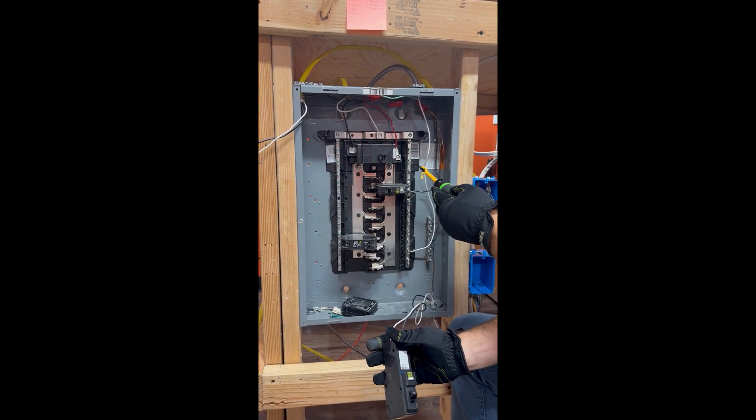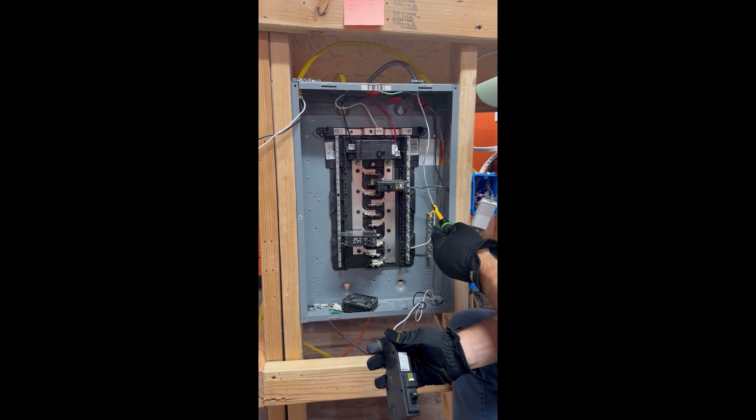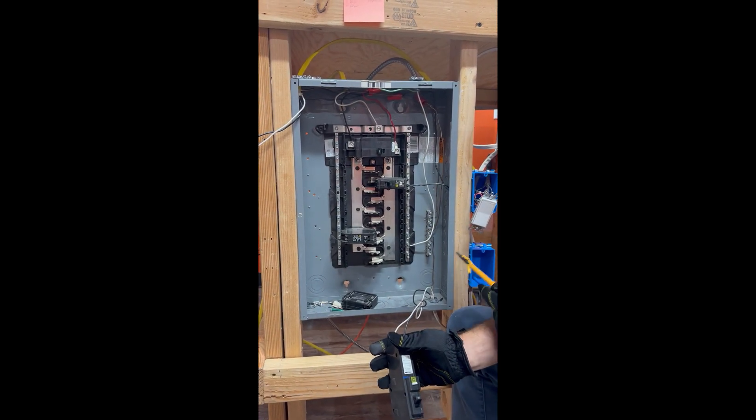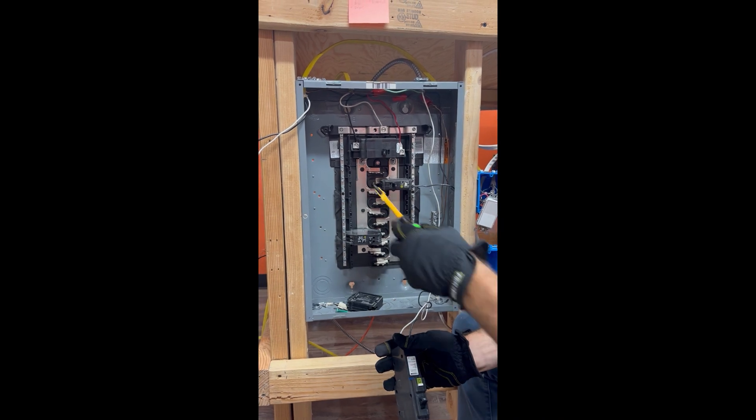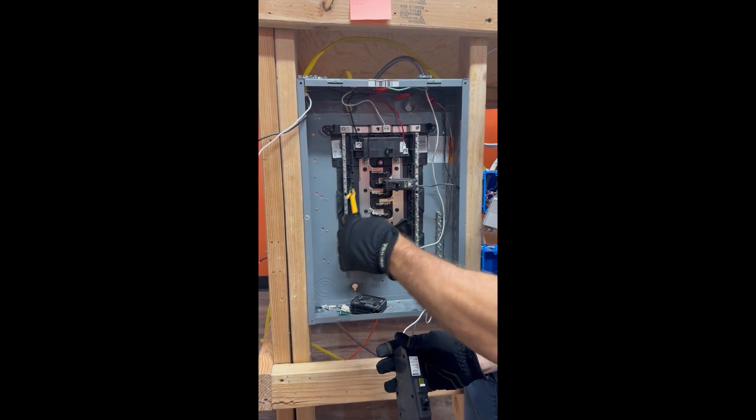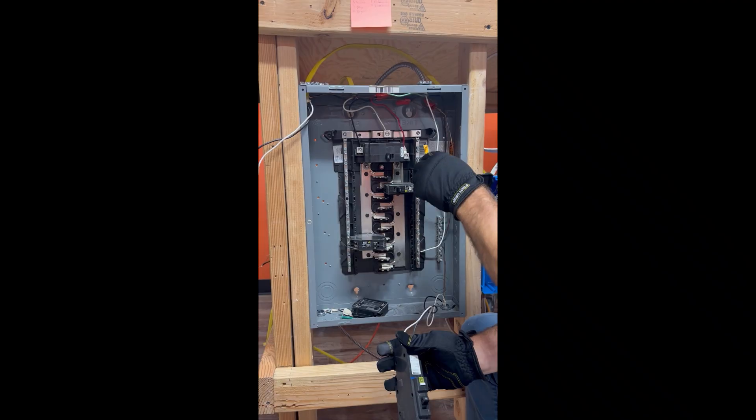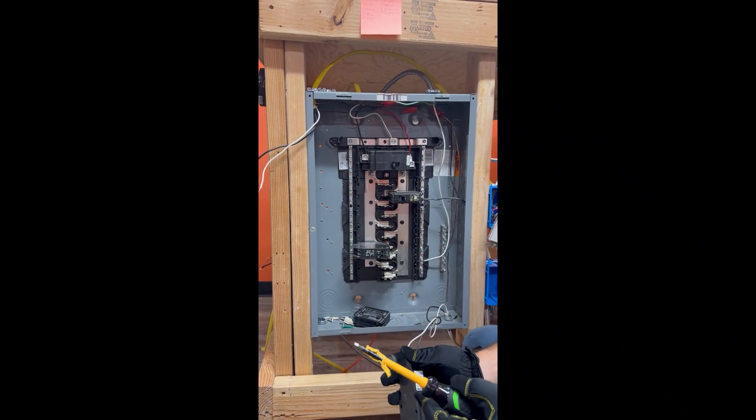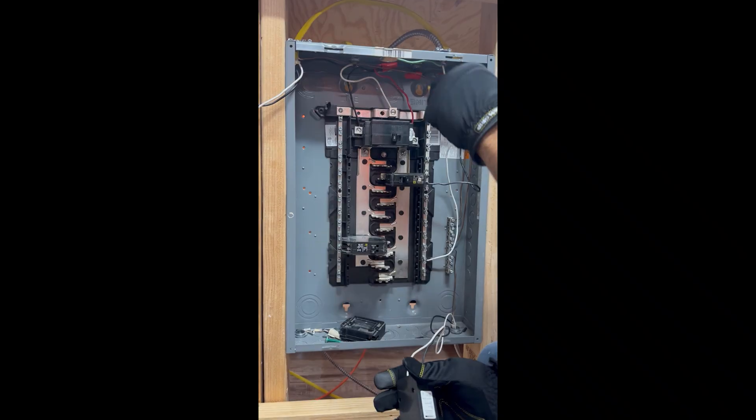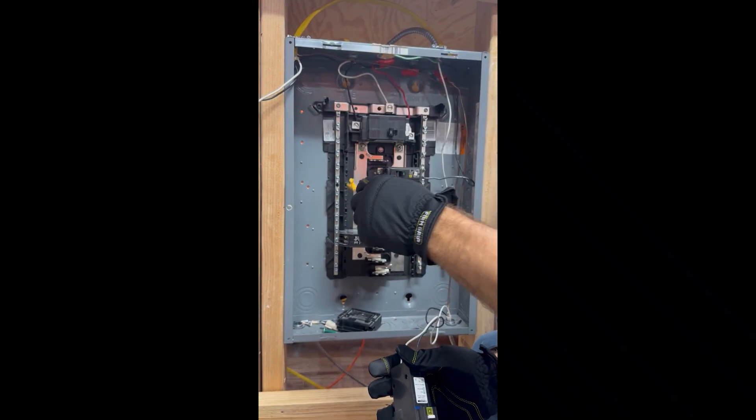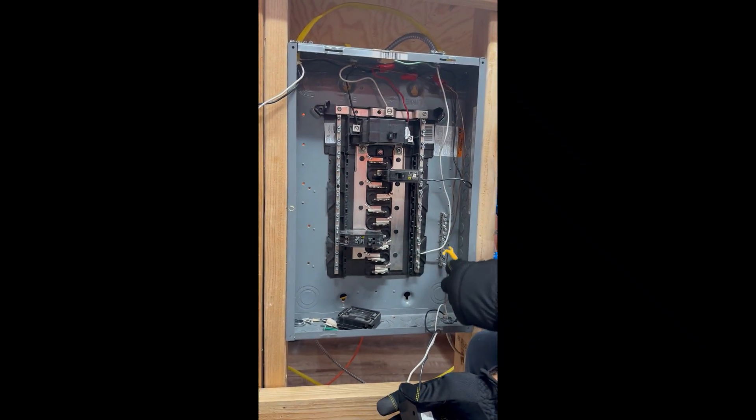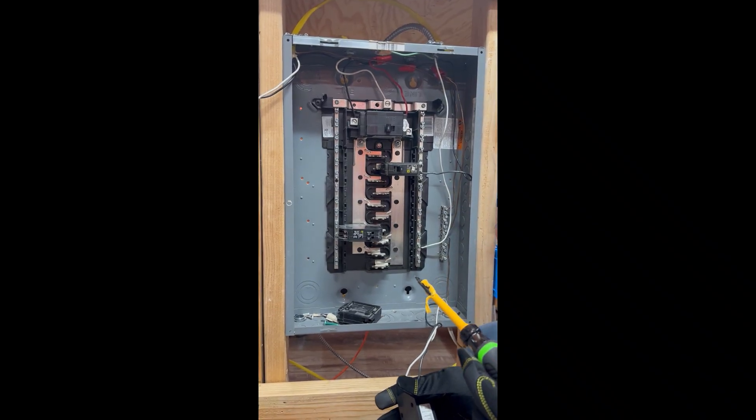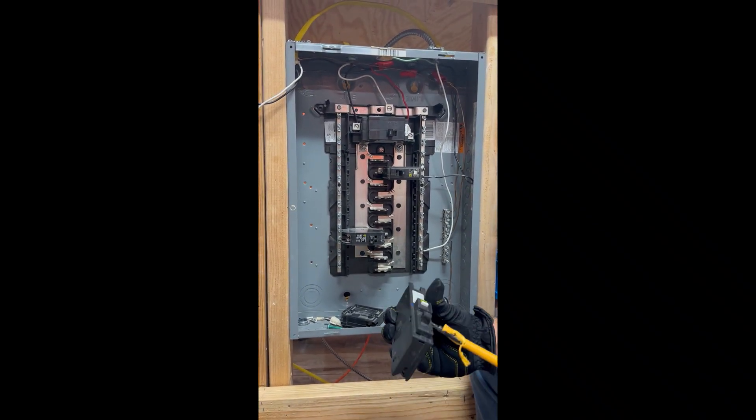As you can see here, both sides of the panel, this is the neutral because it's connected by this bar up here. Okay, this bar goes from this neutral to this neutral bar. All right, the ground you notice is isolated, it's by itself. So whenever we're hooking up a GFCI breaker...